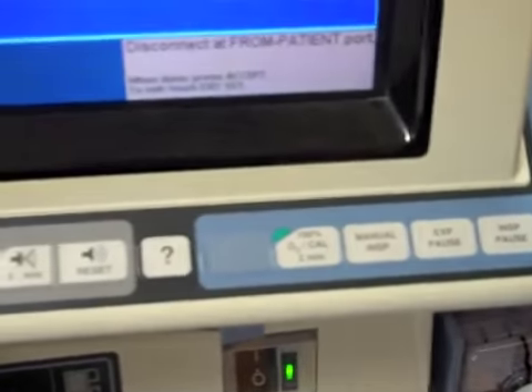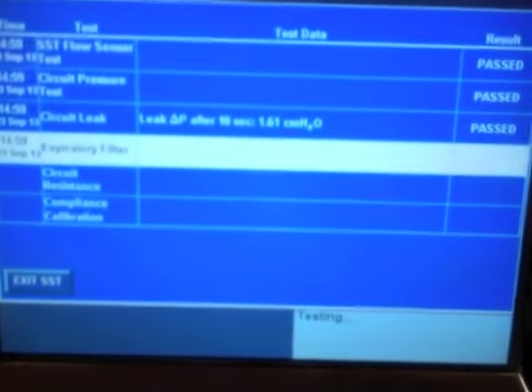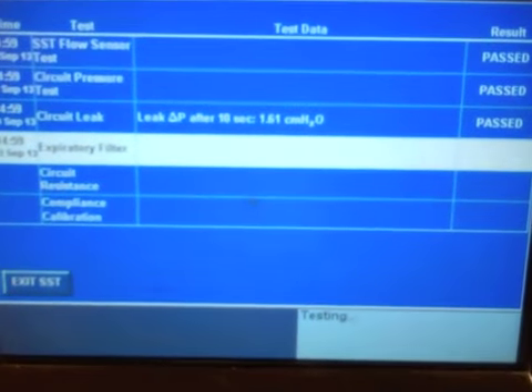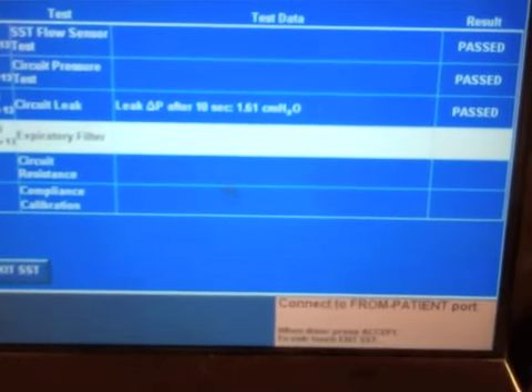We have. It's telling me now to disconnect from patient port. That might seem confusing, but look at what it's asking you to do. We're actually testing the expiratory filter, so from patient port is the expiratory. So I'll actually just pop this off. Okay. Hit accept. Connect to from patient port, so again might be just a little bit confusing, but put that back onto the expiratory side, hit accept.